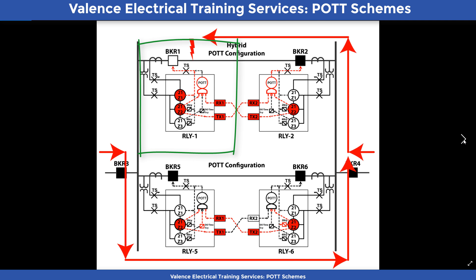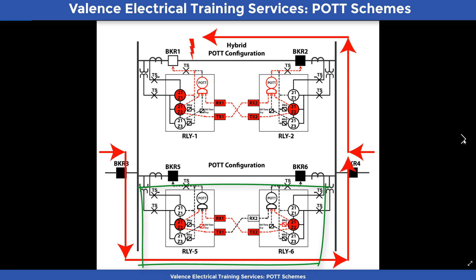Breaker 1 operates with no intentional time delay, which causes a sudden current reversal through Relays 5 and 6. Relay 5 now detects a Zone 2 fault, and it could detect a POTT permissive because Relay 6 may not have had time to release its previous permissive signal yet. But Relay 5 detected a Zone 3 reverse fault a moment before, so the dropout timer will hold the Zone 3 input to the POT scheme on. The NOT logic gate reverses the input, and the POTT scheme cannot operate for five cycles, giving Relay 6 plenty of time to release its POT permissive signal. We have now guaranteed that Relay 2 will always win the race, because Relay 2 will operate after a short time delay, and the fault will be isolated from the system without affecting the non-faulted line. This scheme's weakness has been beaten into submission with logic.